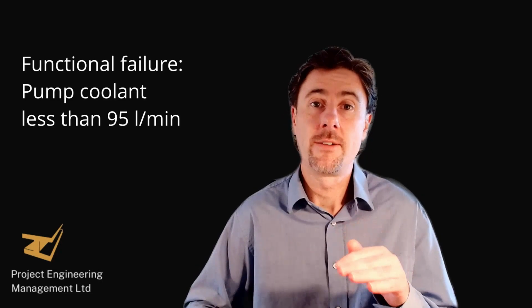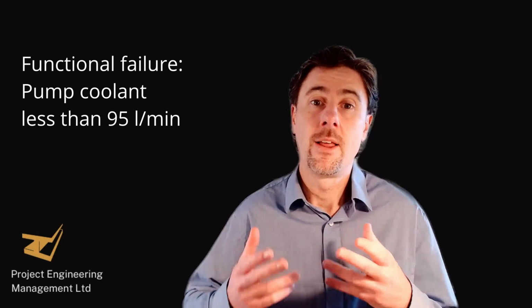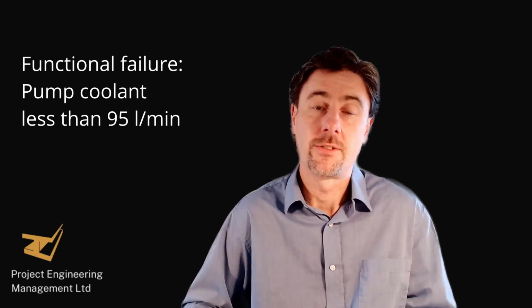So let's say the design of the pump is to flow at 105 litres a minute, but today it's dropped to 100 litres a minute. That's fine, because it's not until it goes to 95 or below 95 that it has technically functionally failed. If that happened, the result would be the engine starts to overheat. So we have to set that specific number of 95 for that reason.